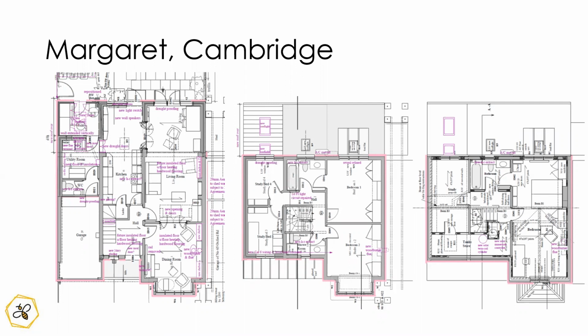You want to keep that separate, don't you? Hot water through the hot water pipe. Okay. And do have a play of the hot water cylinder calculator that you can get your 210 liters up to temperature within a reasonable time limit. I think in social housing you can go up to 4 hours recovery time, so you can play with the recovery time just depending on your own habits, basically.